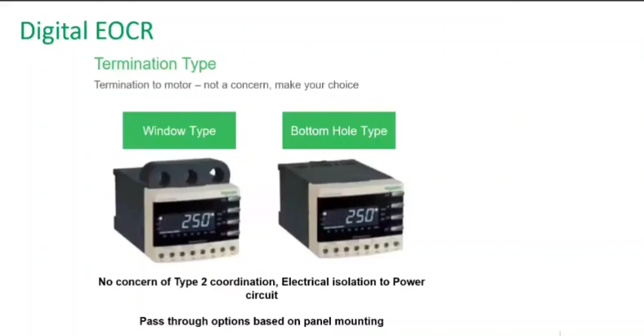There are type 2 coordination charts available with Schneider switchgear. So whether it is your contactor or your particular MCCB protection device, there are type 2 coordination charts available for this product. Some of the key points which I would like to highlight from this product also: individual phase-wise THD monitoring can also be given. So individual phase-wise percentage harmonics you can get to see. There are three fault records available in the product by default. So you can take this for your future maintenance action.